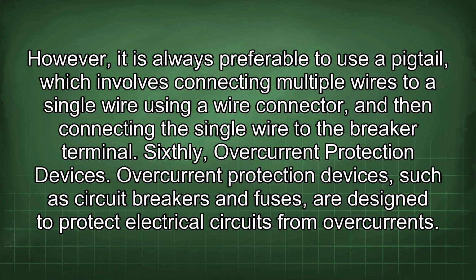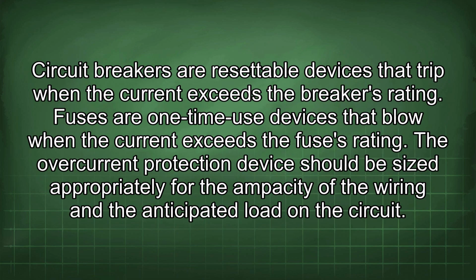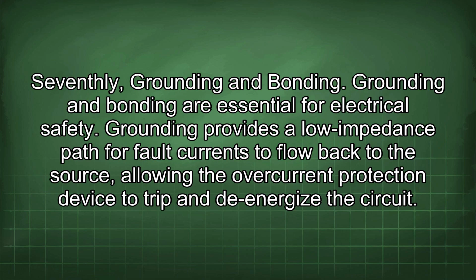Sixthly, overcurrent protection devices. Overcurrent protection devices, such as circuit breakers and fuses, are designed to protect electrical circuits from overcurrents. Circuit breakers are resettable devices that trip when the current exceeds the breaker's rating. Fuses are one-time use devices that blow when the current exceeds the fuse's rating. The overcurrent protection device should be sized appropriately for the ampacity of the wiring and the anticipated load in the circuit. Seventhly, grounding and bonding.